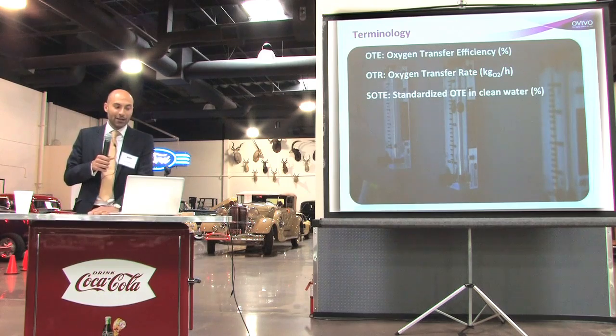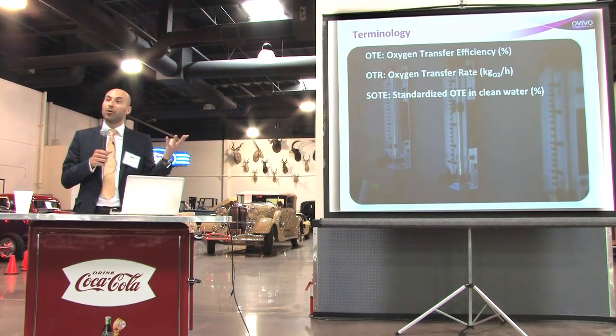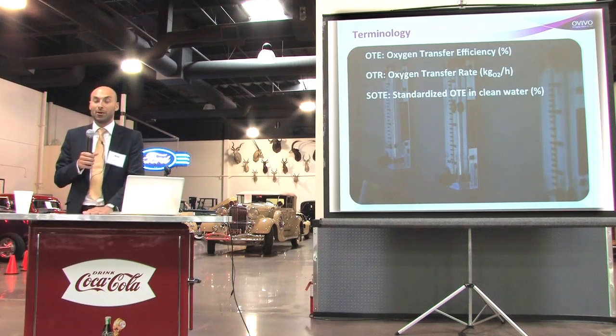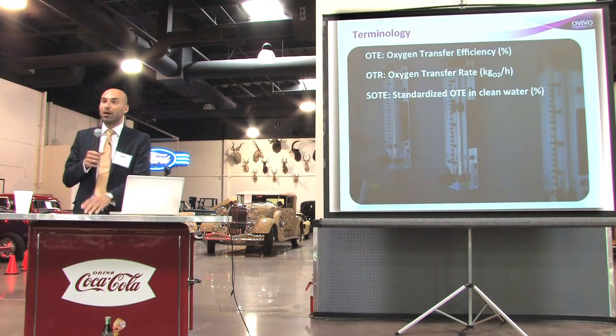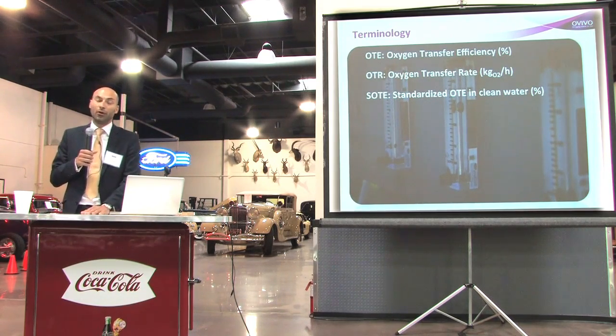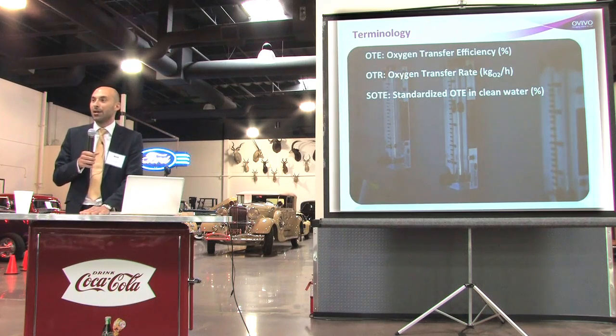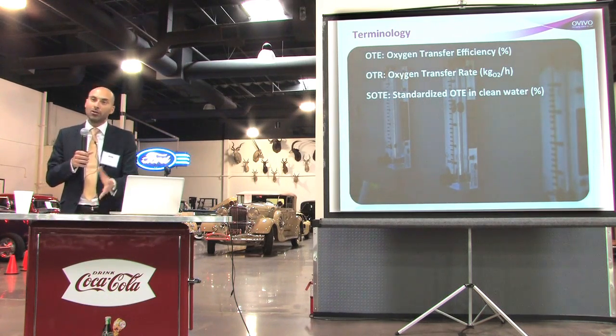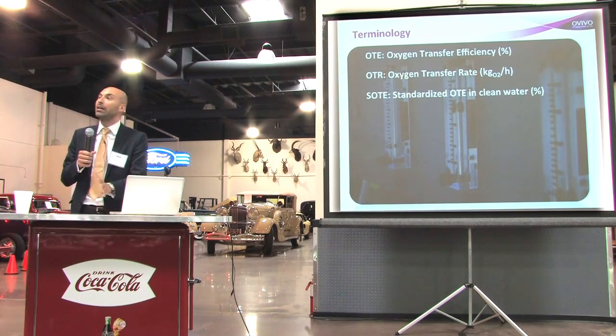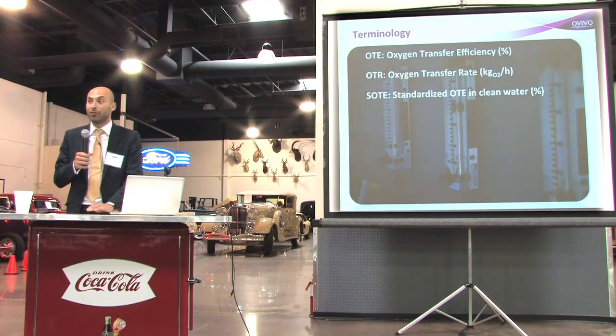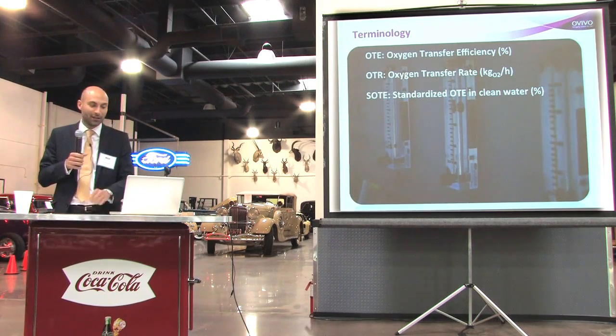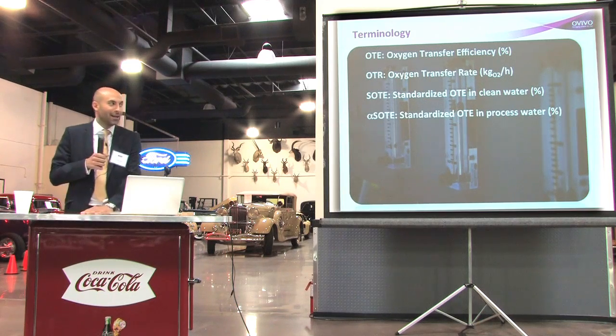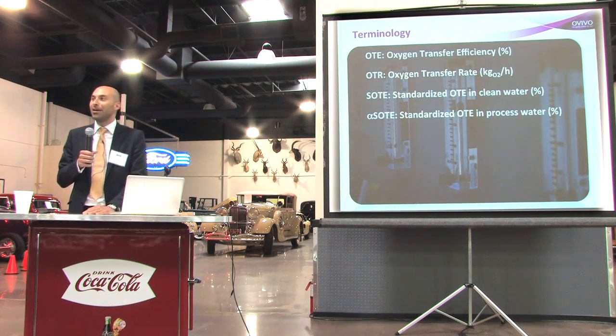You then standardize these values in clean water when you do a clean water test — this is what the manufacturer does according to a protocol with witnesses, providing numbers they can give a warranty for. The standard oxygen transfer efficiency (SOTE) is the value measured in clean water standardized to 20°C, one atmosphere, zero dissolved oxygen, and zero salinity.